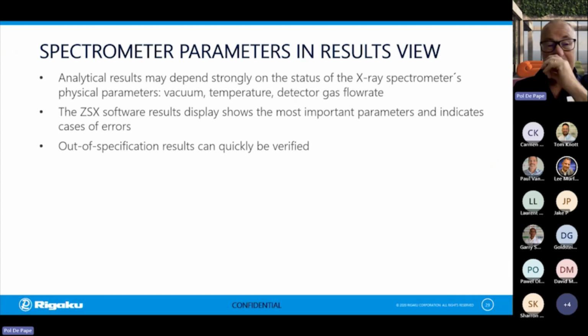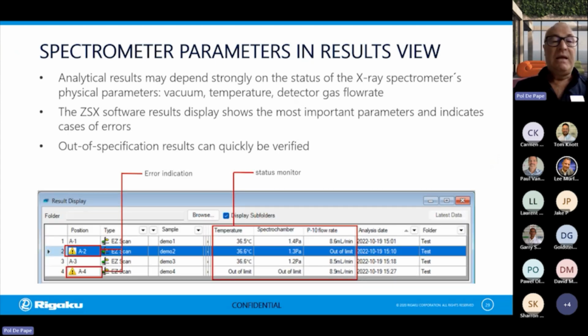So you can quickly see in this window if one result may be out of specification because of one of those three parameters. If we look here, for example, at row number 2, we can see something was wrong here. It was not the temperature. It was not the pressure. Oh, we can see the P10 flow rate, the gas flow rate of the detector, was out of limit. So something may be wrong with the results. This is very helpful to find out, if a result is out of specifications, why it could have been.